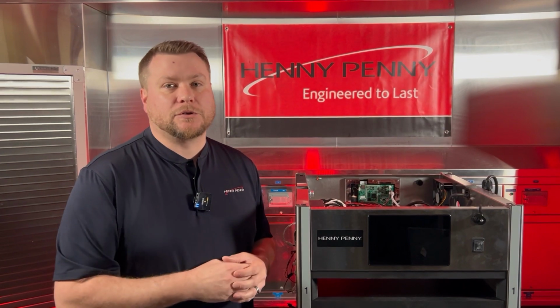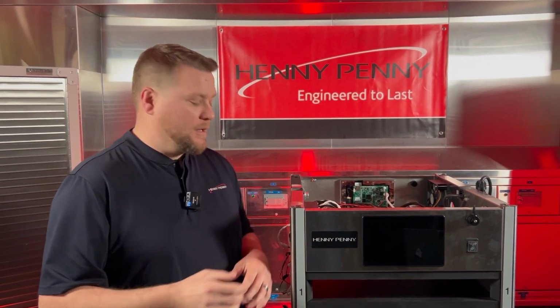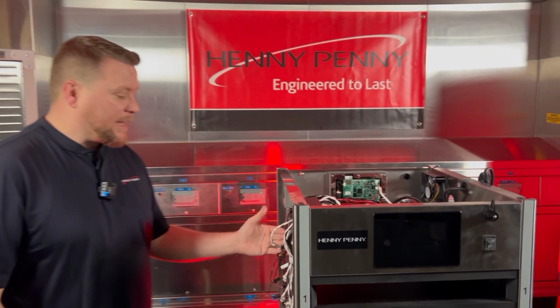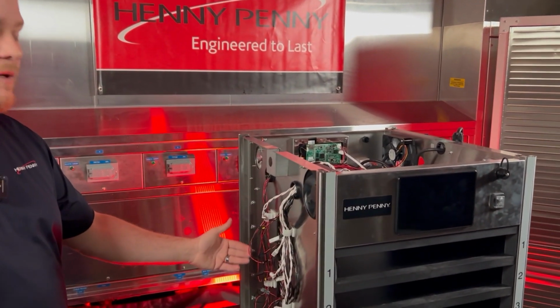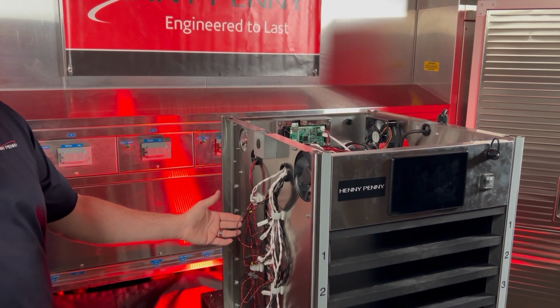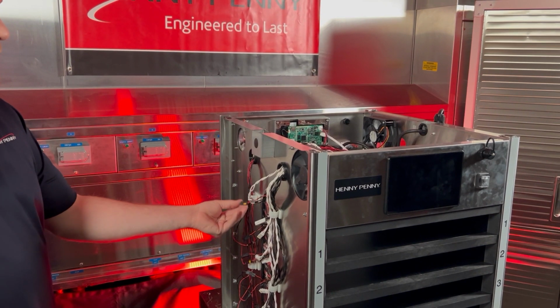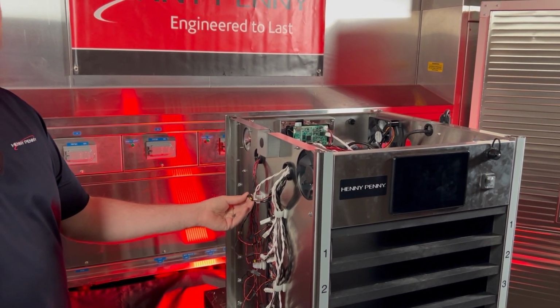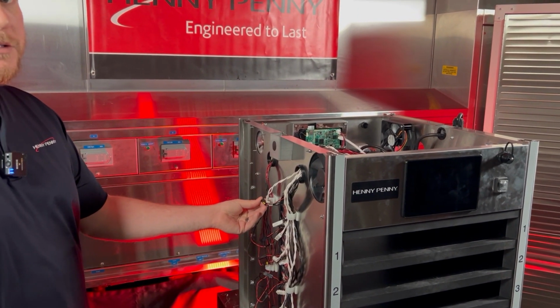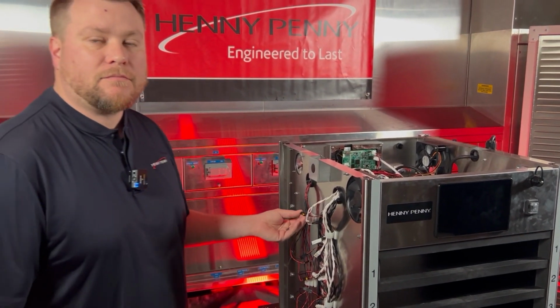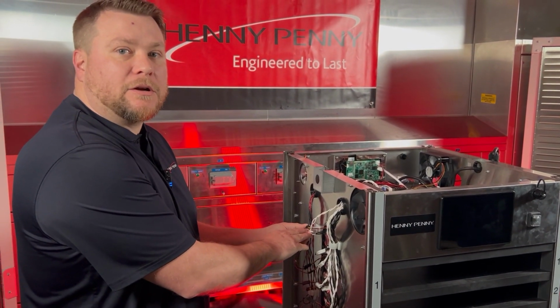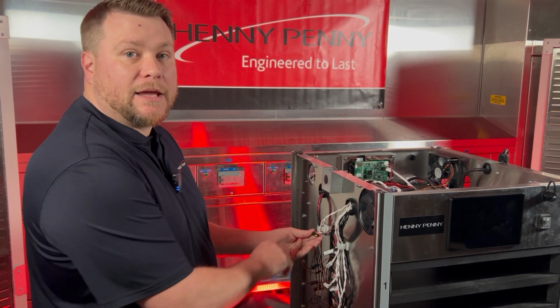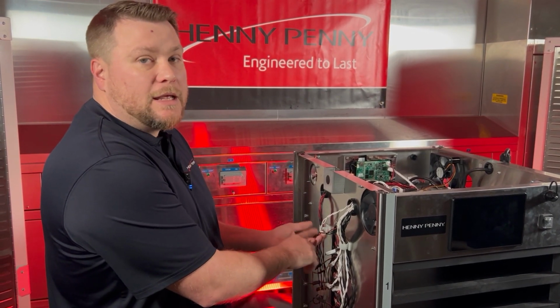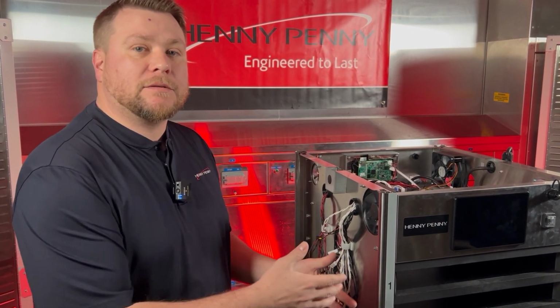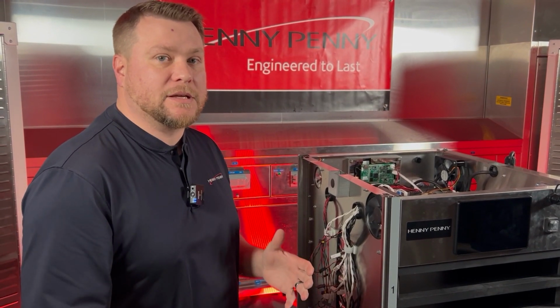So now let's cover troubleshooting on what this looks like. Right here on the side, we have all 12 of our temperature probe wires that are built into our heaters. So what we could do is unplug them. Remember, the error logs will tell us which heater is faulty. We can go ahead and unplug them here, use our multimeter to check for an open circuit. If it shows an open circuit, then we can proceed with replacing that heater assembly.